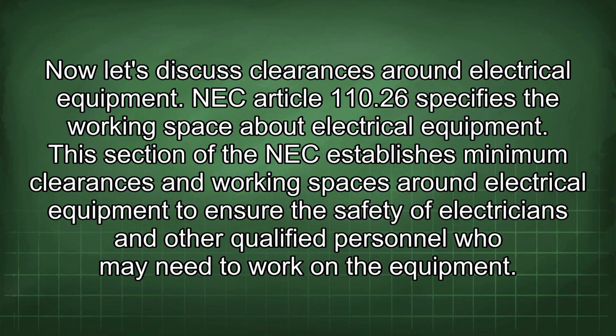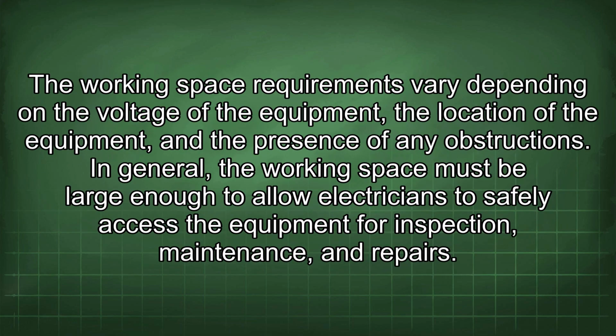NEC Article 110.26 specifies the working space about electrical equipment. This section of the NEC establishes minimum clearances and working spaces around electrical equipment to ensure the safety of electricians and other qualified personnel who may need to work on the equipment. The working space requirements vary depending on the voltage of the equipment, the location of the equipment, and the presence of any obstructions. In general, the working space must be large enough to allow electricians to safely access the equipment for inspection, maintenance, and repairs.